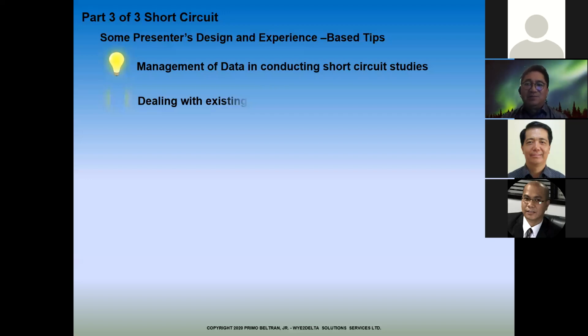That's just the repercussion, but it's also a solution. But you cannot have an IS limiter and a reactor at the same time. If you want to put a reactor, you have to put it in series to the generator itself, not to the tie - limit it at the actual contributor. So if the cost issue is under-rating the current because of those two generators, you may opt to put 2 reactors in series on each one.